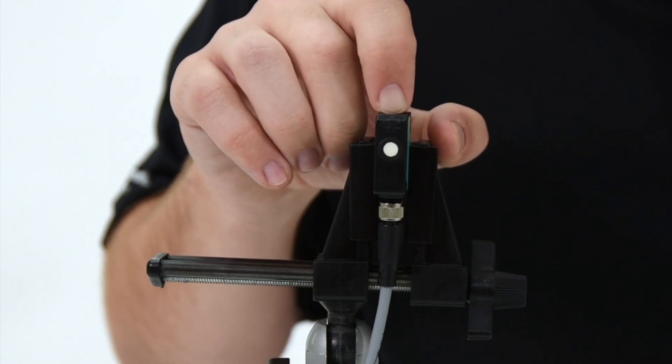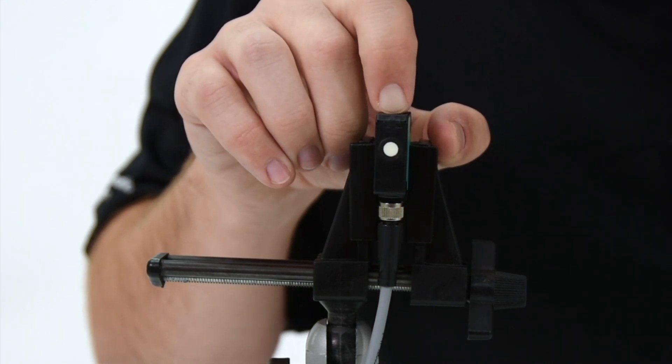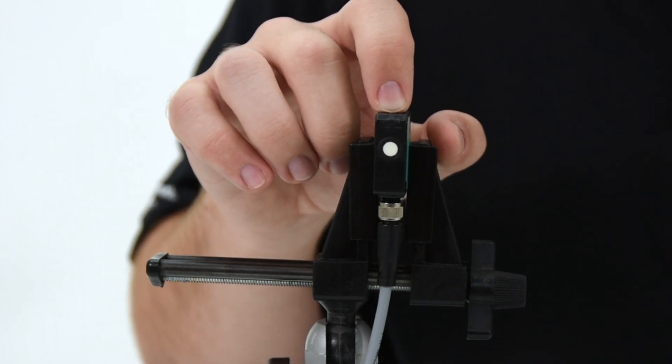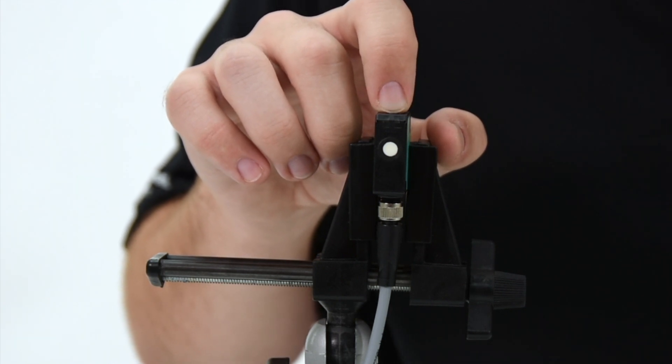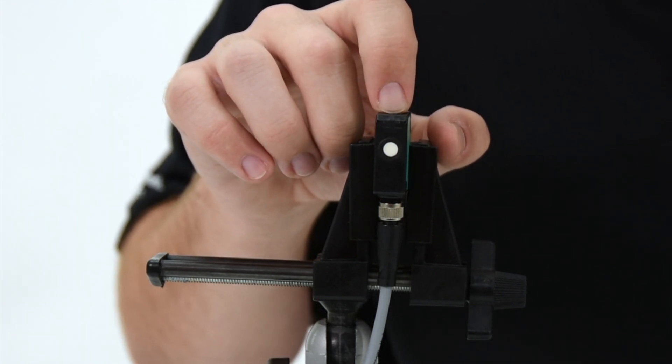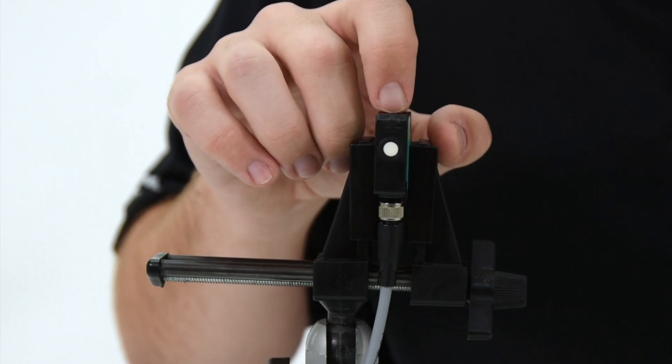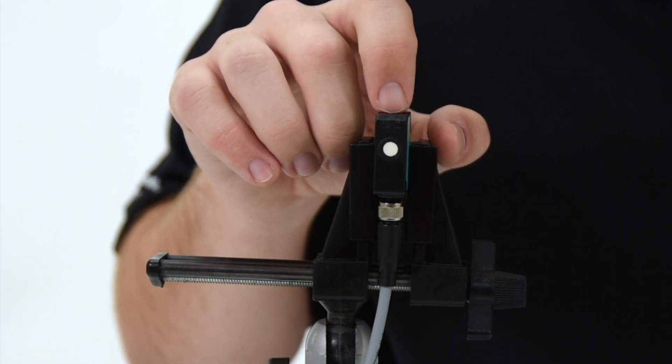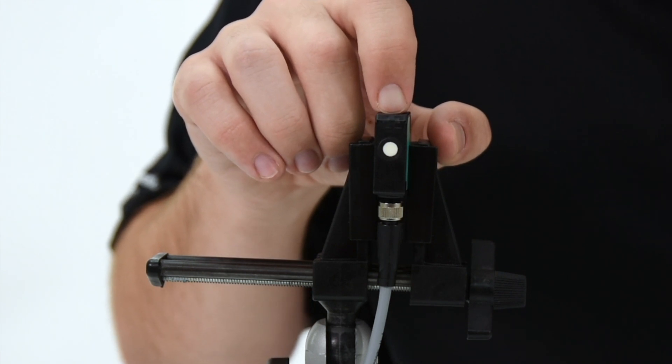To move on, hold the button for two seconds. Now that it is flashing yellow, we can select the output logic for the sensor. One flash indicates normally open, and two flashes indicate normally closed. To cycle in between, simply press once. To move on, we will hold again for two seconds.